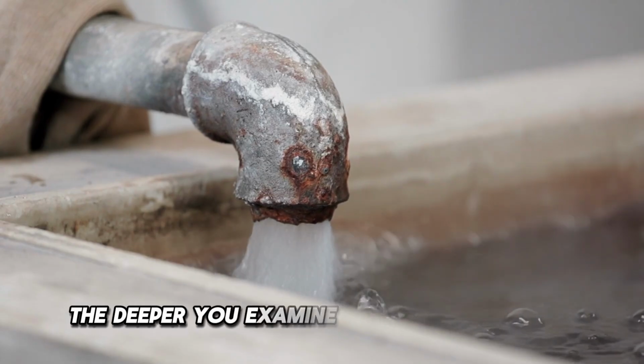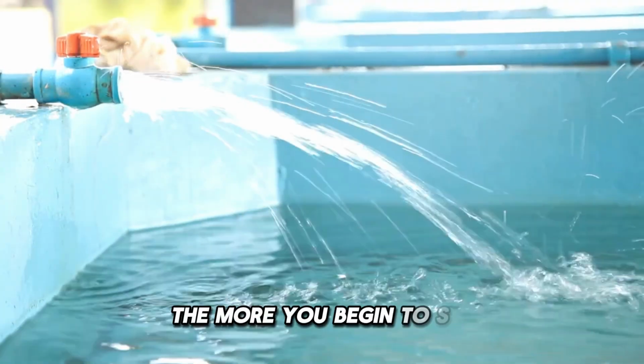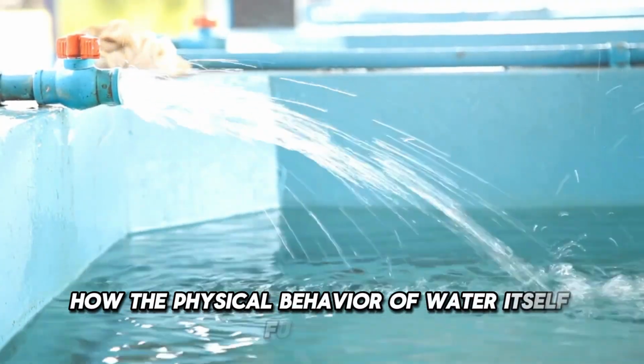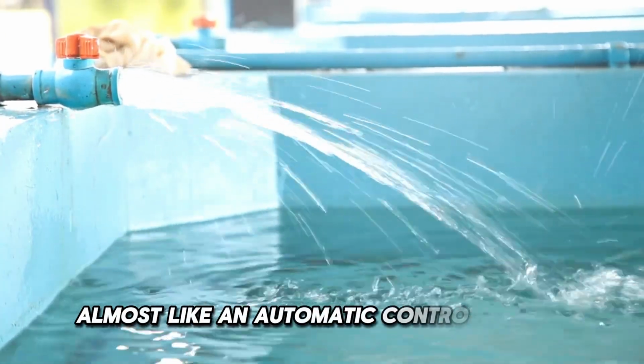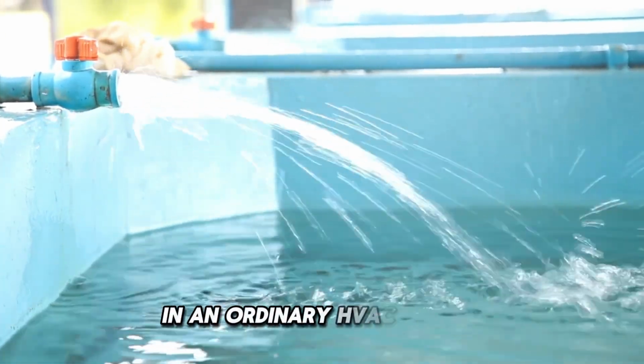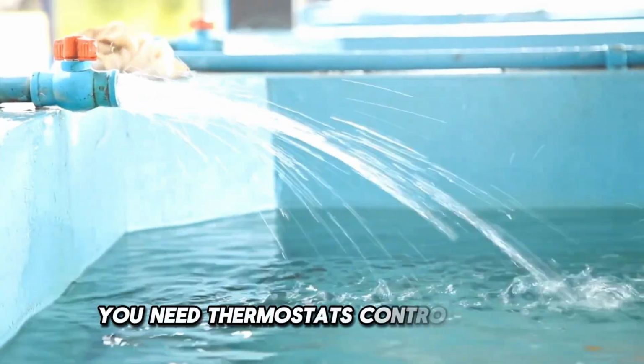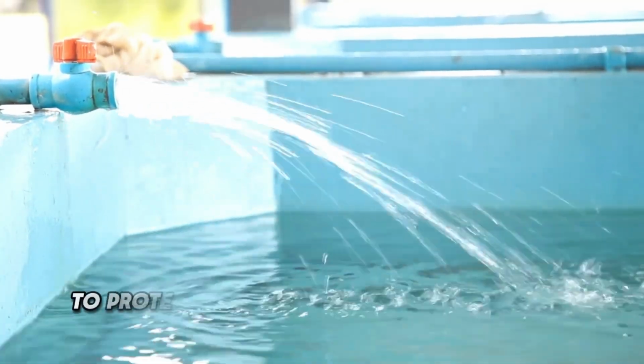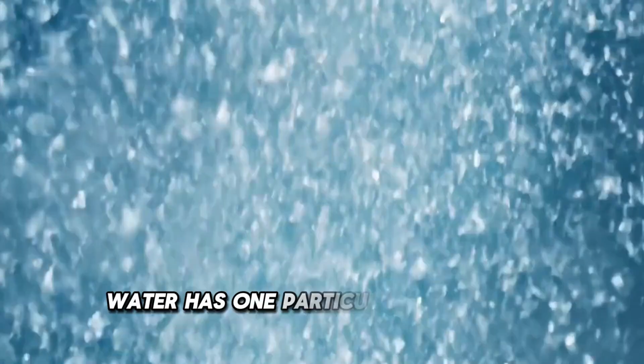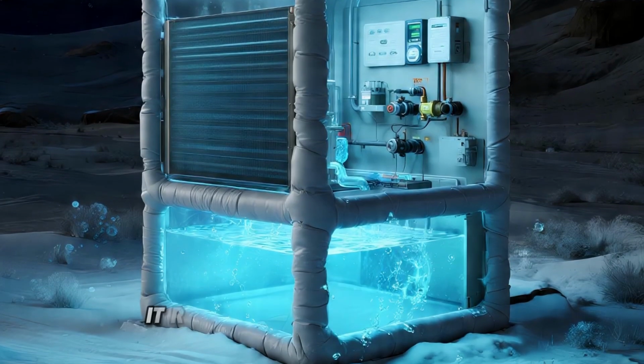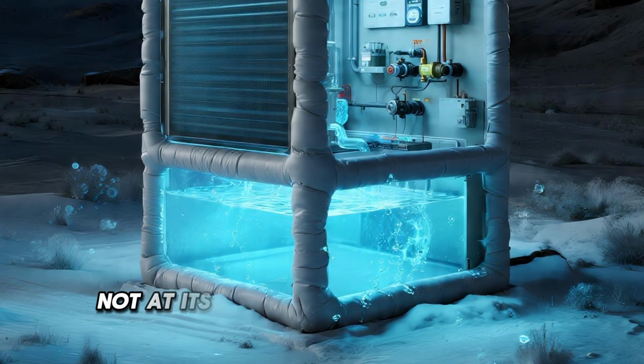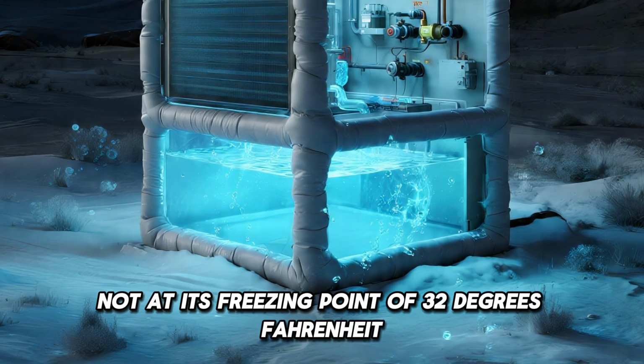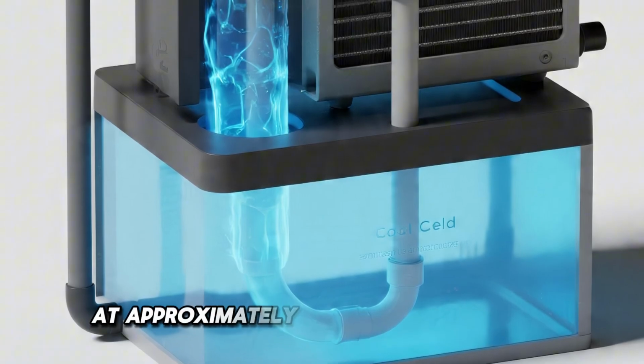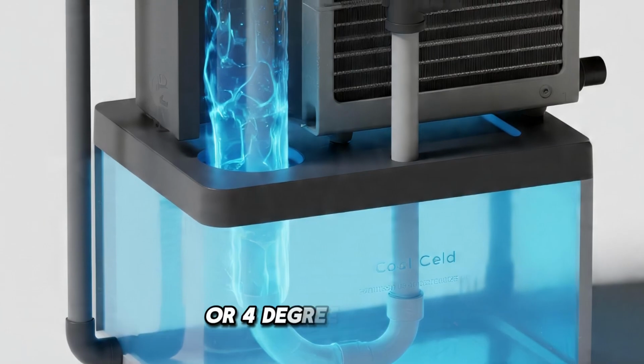The deeper you examine Steve Baer's designs, the more you begin to see how the physical behavior of water itself functions almost like an automatic control system. In an ordinary HVAC system, you need thermostats, control boards, and motorized valves to protect equipment from freezing during winter. The cool cell accomplishes much of this without moving parts. Water has one particularly unusual characteristic. It reaches its maximum density not at its freezing point of 32 degrees Fahrenheit, but slightly above it, at approximately 39 degrees Fahrenheit, or 4 degrees Celsius.